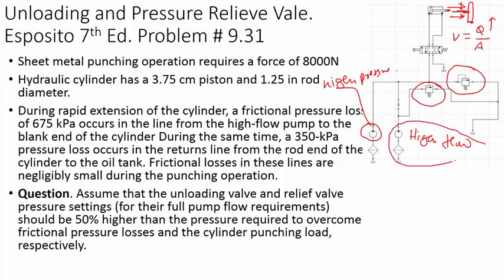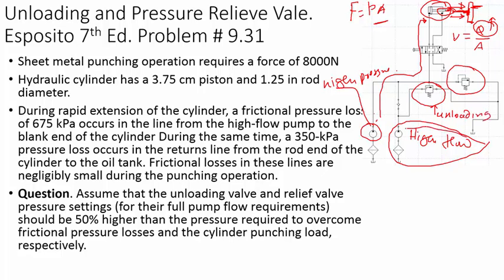This high-flow pump moves the punch towards the sheet metal. When the punch touches the sheet metal, we need very high force, which comes from high pressure. This high-pressure pump maintains very high pressure and produces high force. It doesn't create much flow because when the punch contacts the sheet metal there is no movement needed. The unloading valve then unloads all the flow, dumping it back to the reservoir.